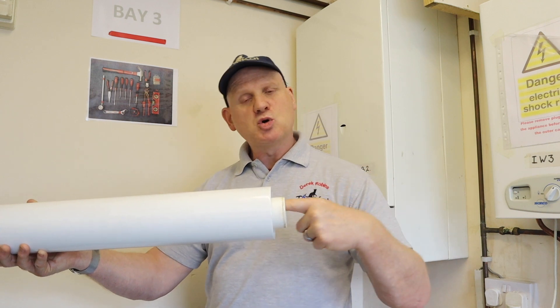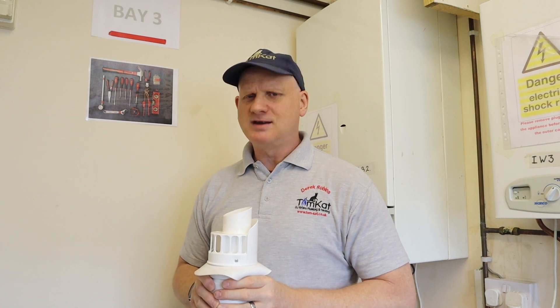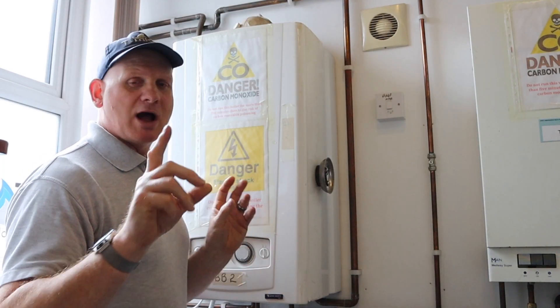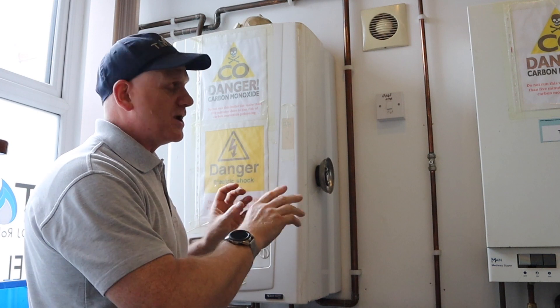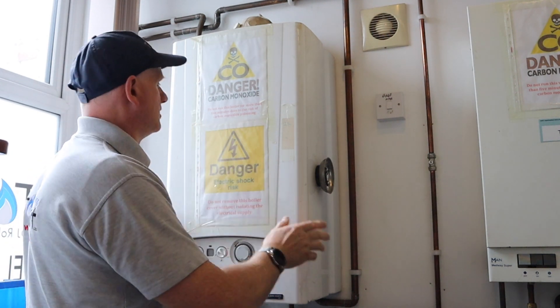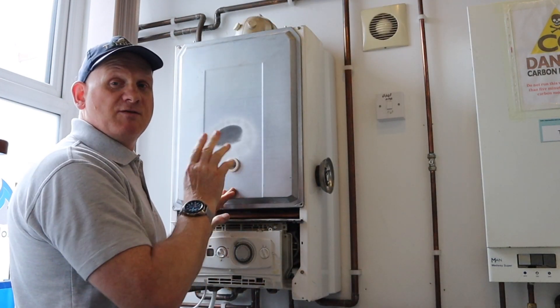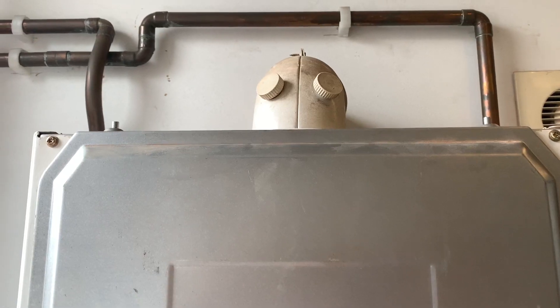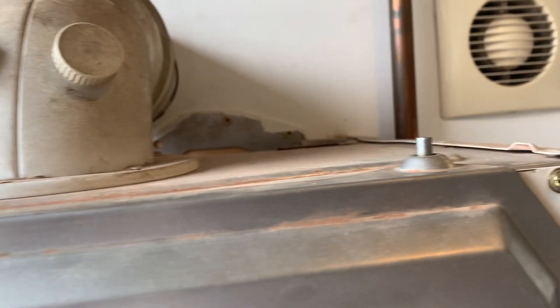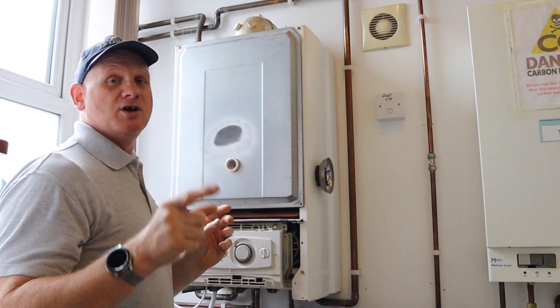Positive pressure pushes the products out; negative sucks the air in. All boilers now are negative pressure, so let's look at the telltale signs. If we take the main front cover off, we can see the combustion chamber cover. There are just two little clips at the top, two little pegs really, and two screws holding it in — that's a good first indication this is under negative pressure.